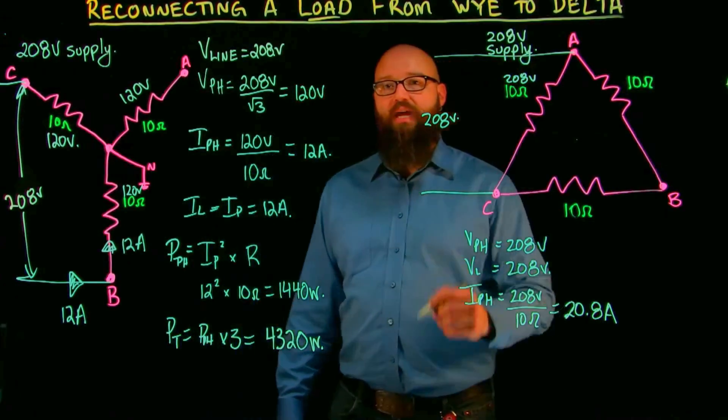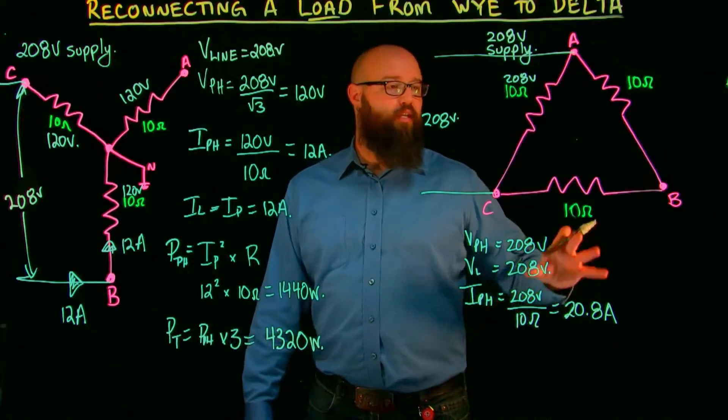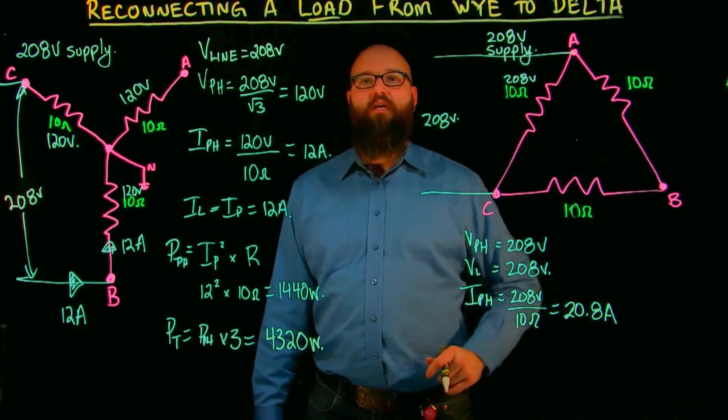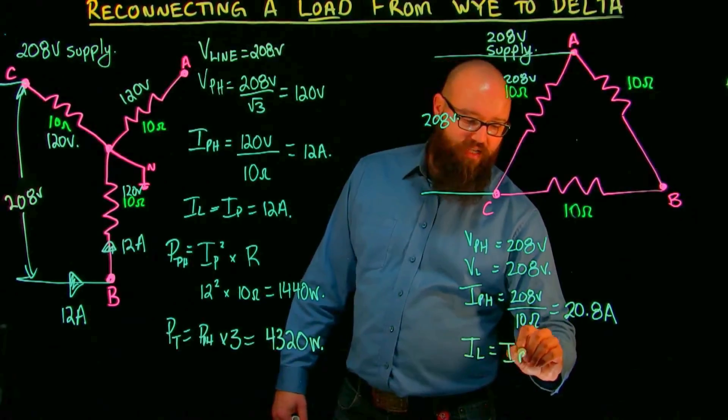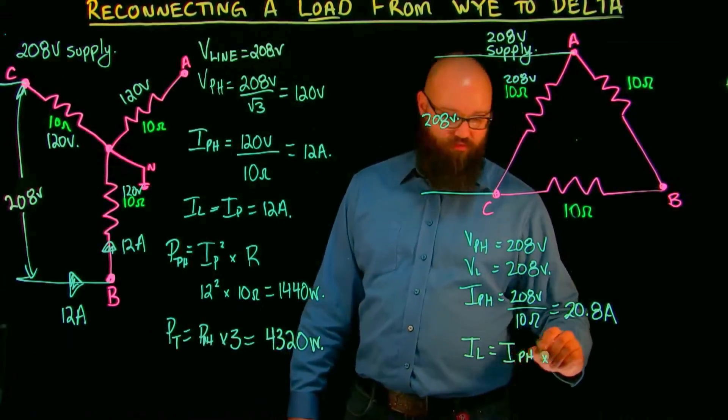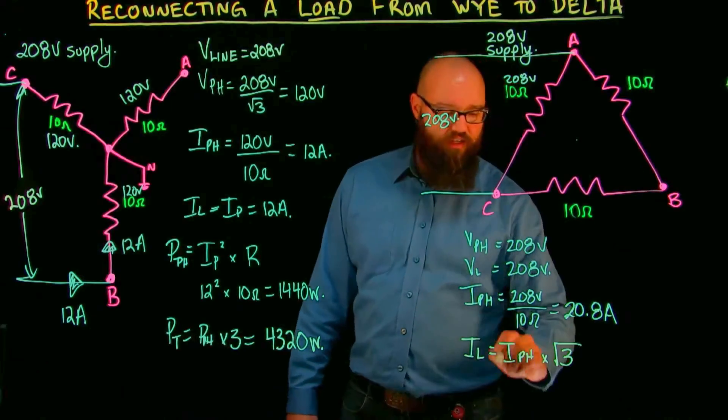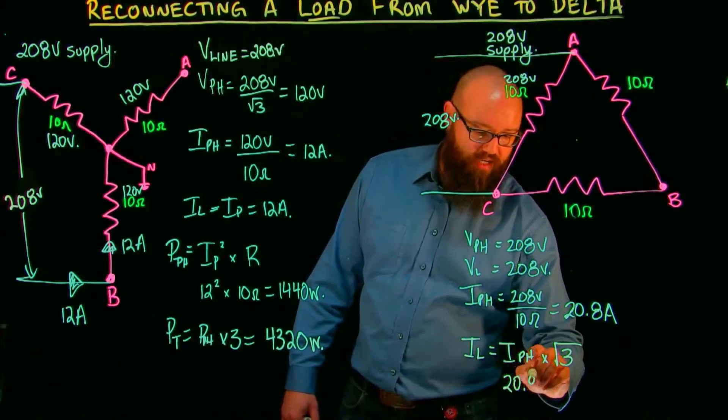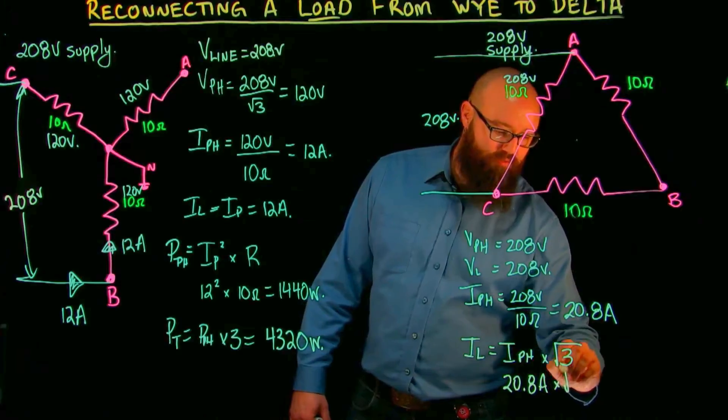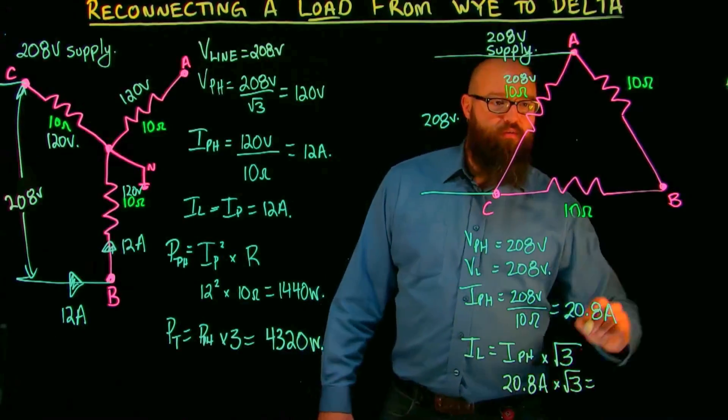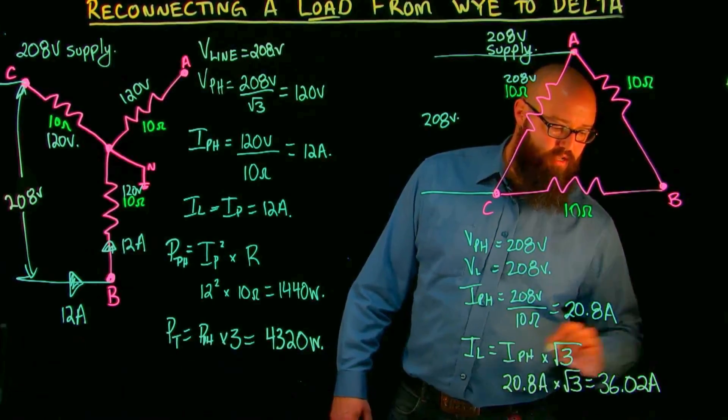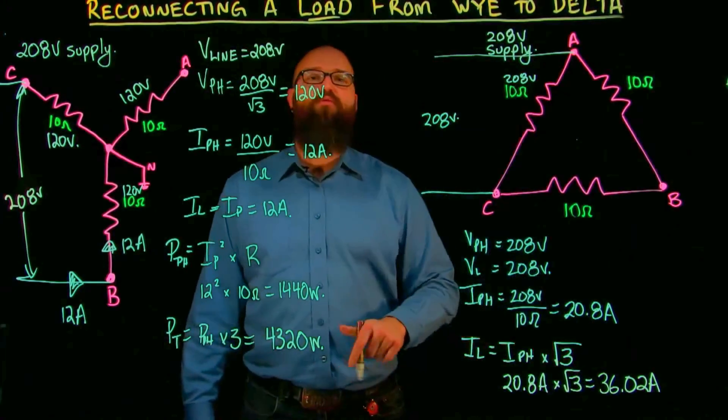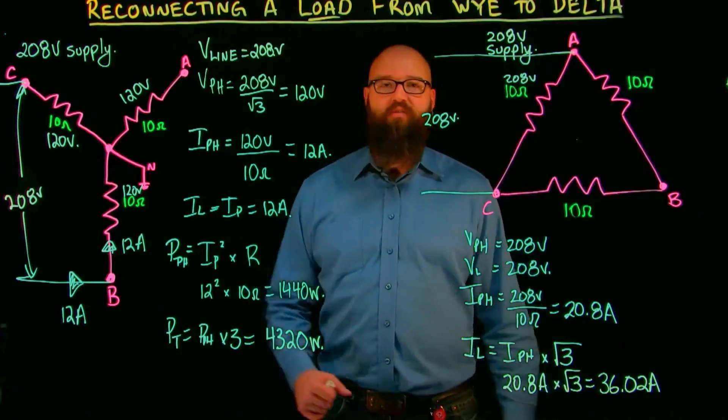Now to find line current, what we know when we're dealing with a balanced delta connected circuit is this: I line equals I phase times root 3. In this case, we have 20.8 amps times root 3 equals we should see somewhere around 36.02 amps.